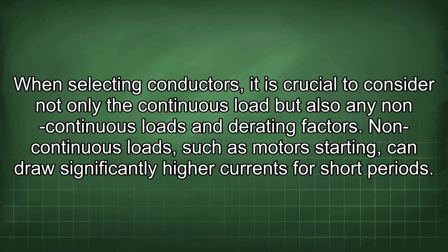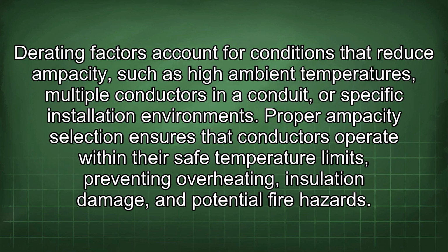When selecting conductors, it is crucial to consider not only the continuous load but also any non-continuous loads and derating factors. Non-continuous loads, such as motors starting, can draw significantly higher currents for short periods. Derating factors account for conditions that reduce ampacity, such as high ambient temperatures, multiple conductors in a conduit, or specific installation environments.